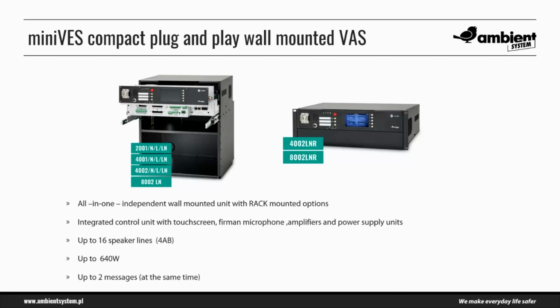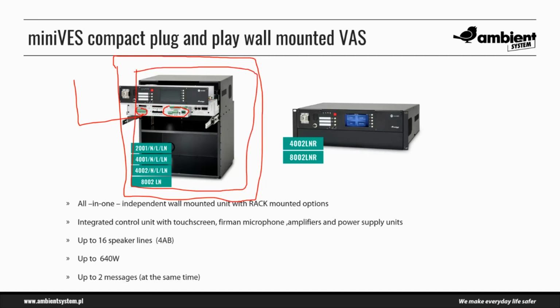Mini and MIDI are, as the name suggests, designed for small and medium installations. Especially mini-VES, which is designed so that it's contained in one housing, and only requires cables to be connected from the field, like speaker cables and cables connecting to the fire detection, into these terminals. The system is all-in-one, so it includes all components. It's pre-designed already, with a closed architecture. There are no modular elements in it, making it very easy for installers and commissioning engineers to implement in the building.